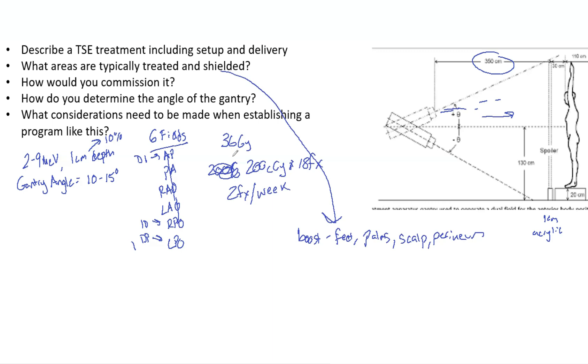For shielding, you want to use extra shielding for the eyes, the nails, and the top of the scalp, because those are most likely to show some biological and negative effect due to the radiation. Normally, according to papers, when you use that acrylic or plexiglass degrader, you can get ±4% horizontally in terms of dose uniformity and ±8% vertically for dose uniformity, which is pretty good. Also, ideally when you move this gantry, you're going to get less than 4% x-ray contamination.